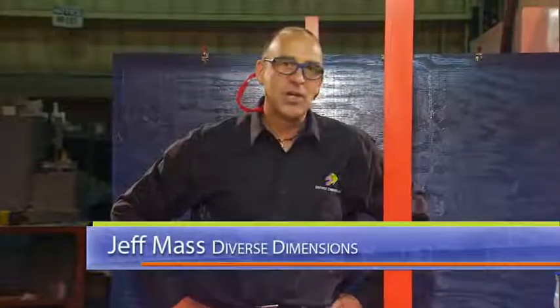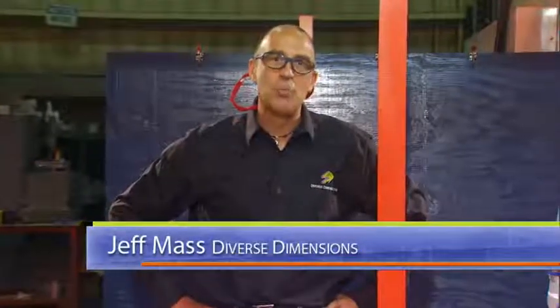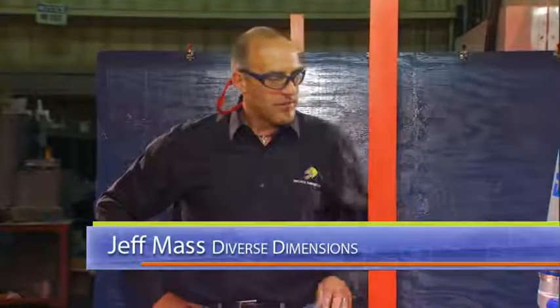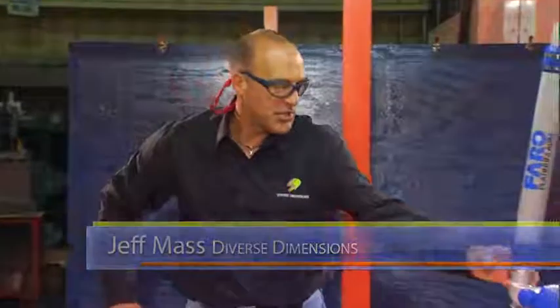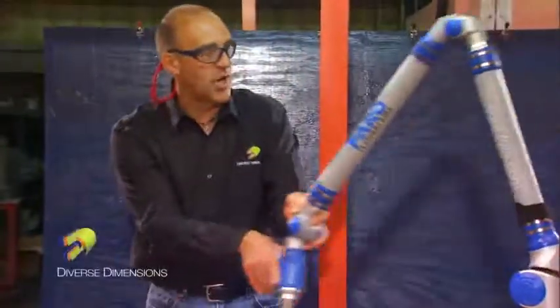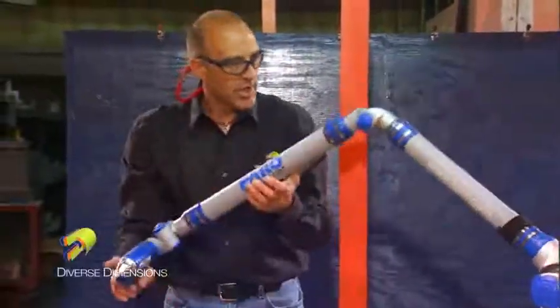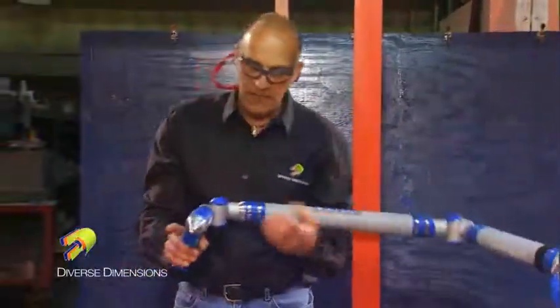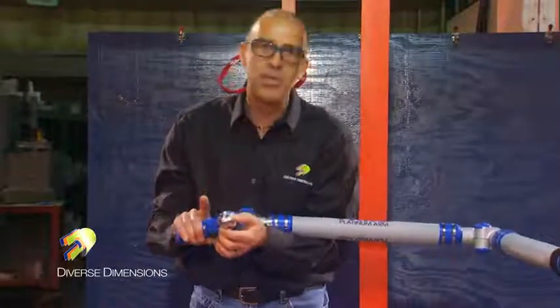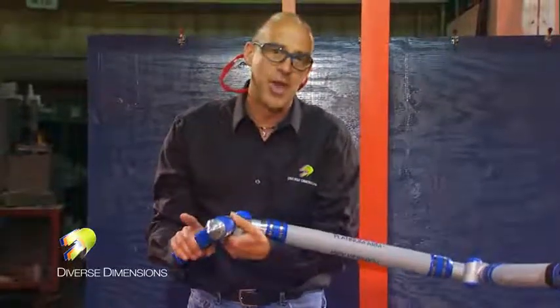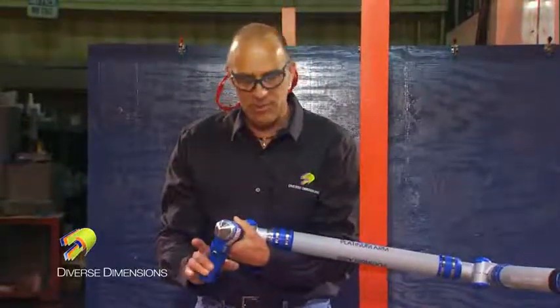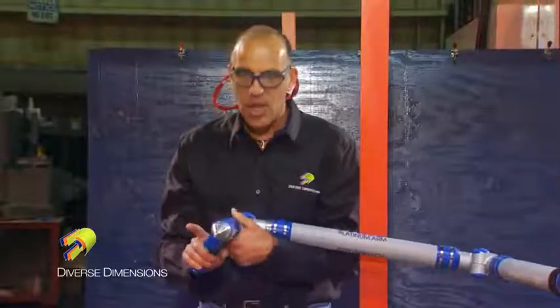But before I do that, I wanted to show you guys a single point calibration. What I've done is yesterday we were doing some laser scanning with this arm. So I peeled off the LLP and I've got the 6mm probe on there now. I'd like to do a calibration before I jump into the measurement session.